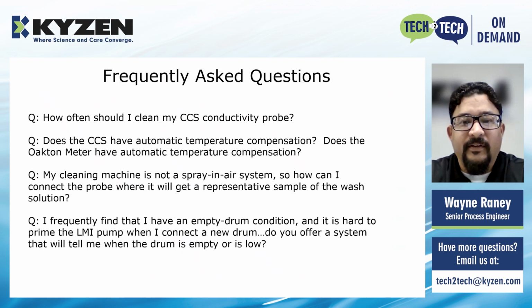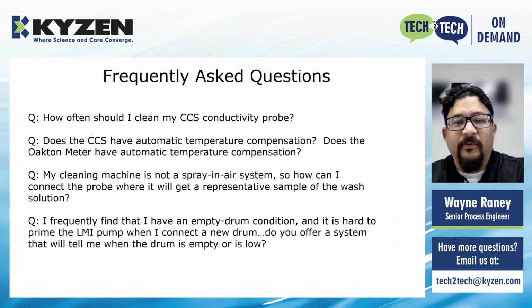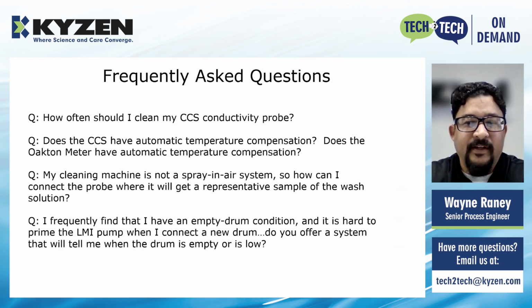A few of the commonly asked questions is how often should I clean my conductivity control system probe? Well, if you're performing calibration check and your readings are correct, then you don't really need to clean the probe. But once you start noticing that you need to calibrate the probe after a calibration check, then that'll give you an idea how often to clean the probe. But honestly, I would clean it at least twice a week, regardless.